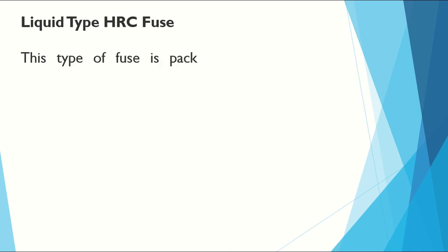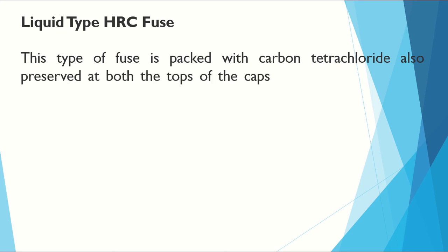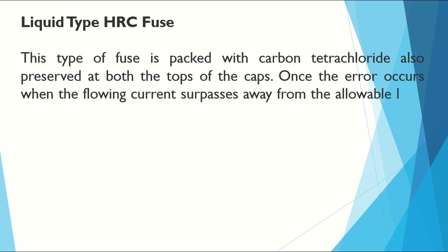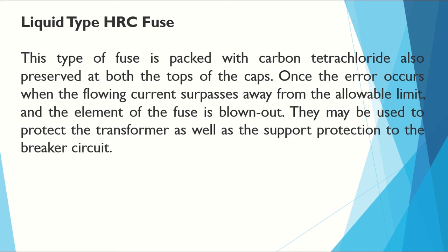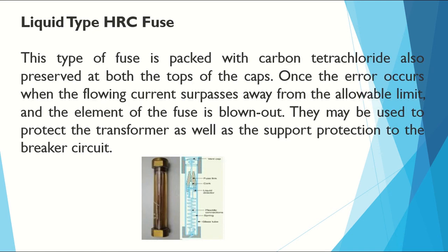Liquid type HRC fuse — this is also a high voltage fuse. This type of fuse is packed with carbon tetrachloride and preserved at both end caps. When an error occurs and the flowing current surpasses the allowable limit, the fuse element is blown out. They may be used to protect transformers as well as provide backup protection to breaker circuits.